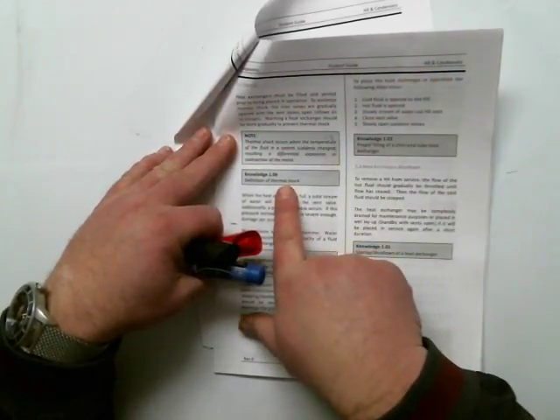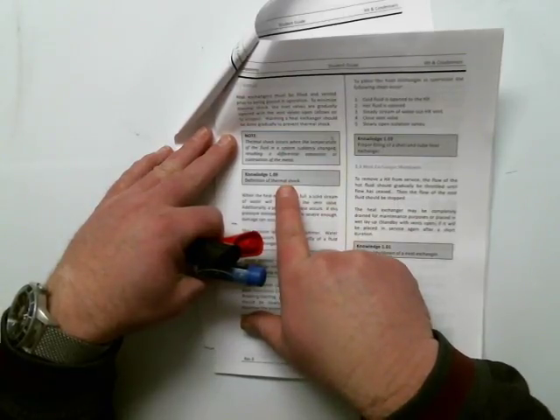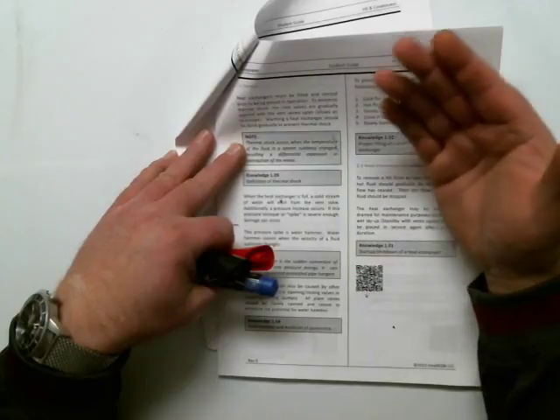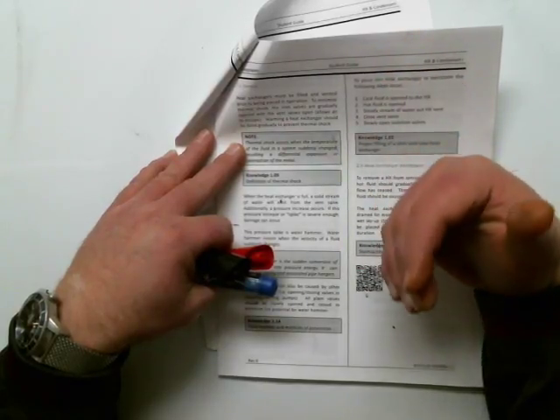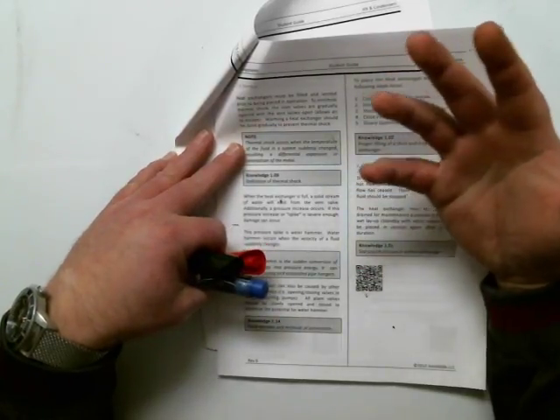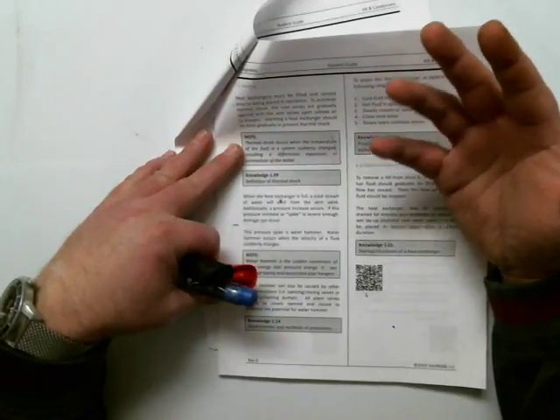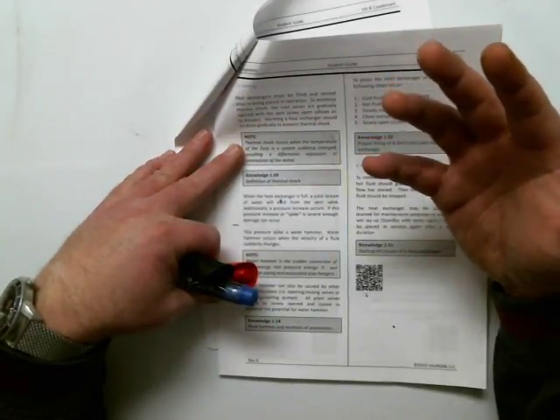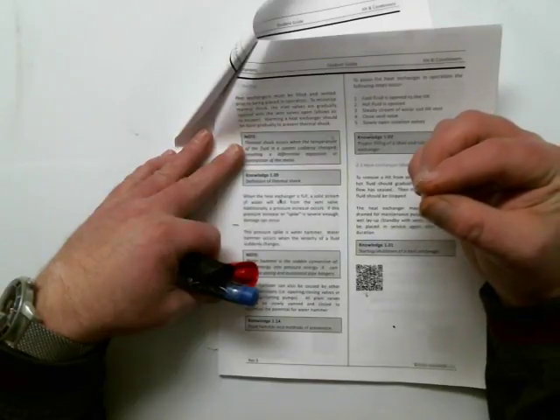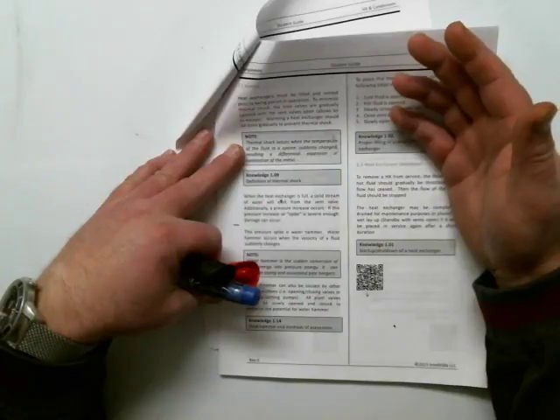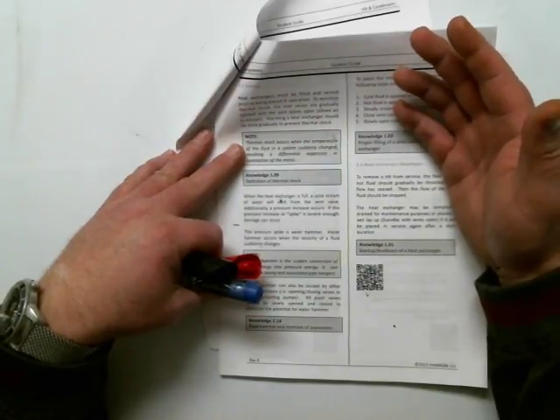See this right here, this knowledge requirement says, hey, what's the definition of thermal shock? And we need to prevent it. So what it is, it's when we have a difference in temperature that can actually cause a sudden contraction or expansion of the heat exchanger, and very often you can damage it by cracking welds.